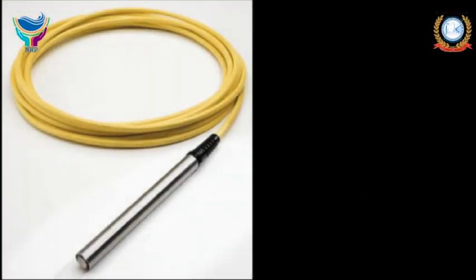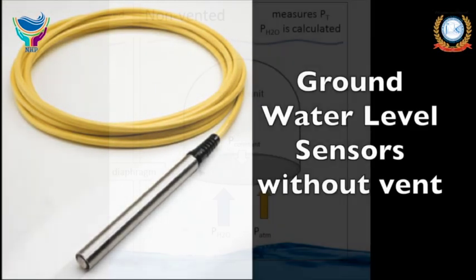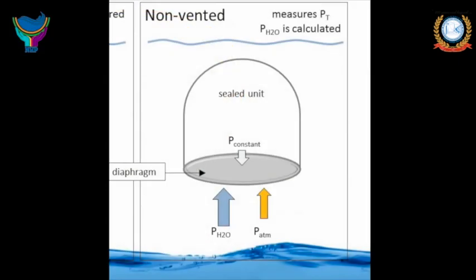The groundwater level sensors without vent. Non-vented loggers are barometrically compensated using a barometric pressure logger and a simple software function to perform the mathematics. Barometric pressure values can also be obtained from weather stations within a 10-mile radius.